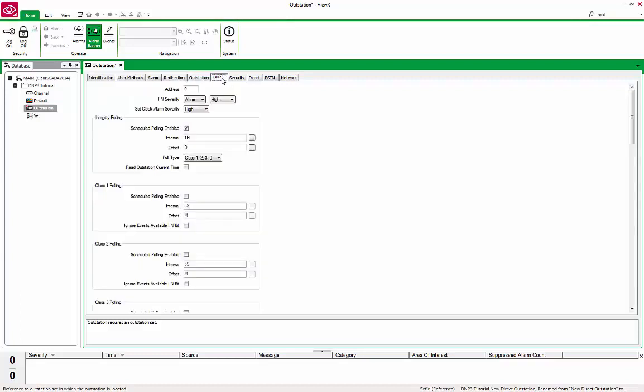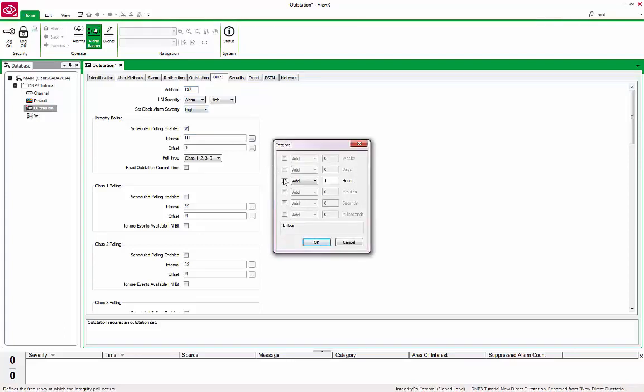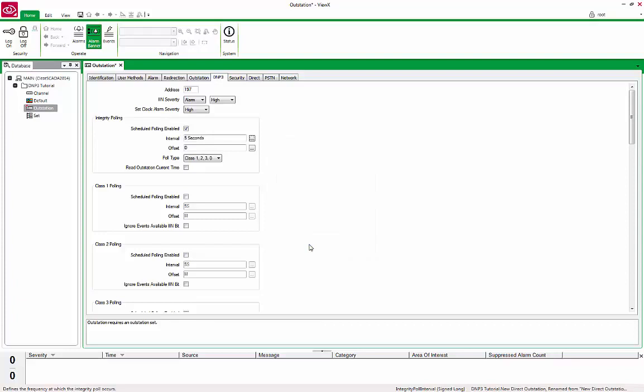Even though DNP3 protocol has various configurable settings available, we will only work with a few basic ones. In most cases, the default values will work just fine. Further detailed information may be found in the online help for each field by pressing F1 or by reading the tool tips provided for each field as you hover over that field. Set the Address field to 197. This is the DNP3 address of the remote device. Set the Integrity Polling Interval to 5 seconds. You can do this by either entering 5S or using the Browse button to configure the time. This asks ClearSCADA to interrogate the device for both timestamped event and current or static data every 5 seconds.